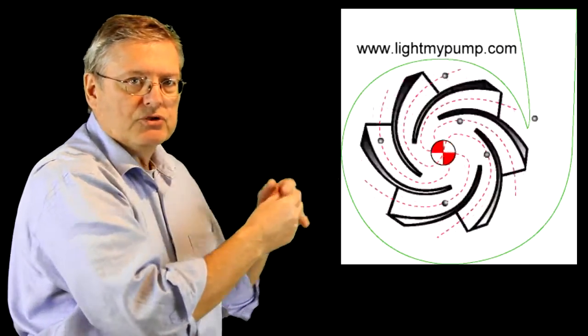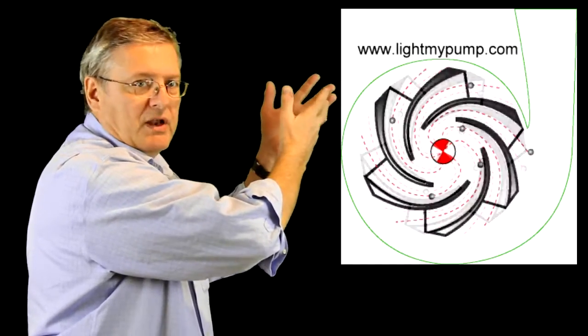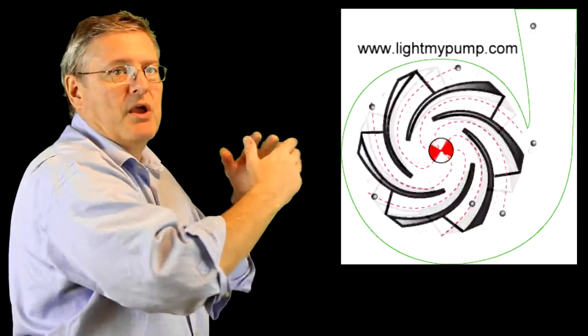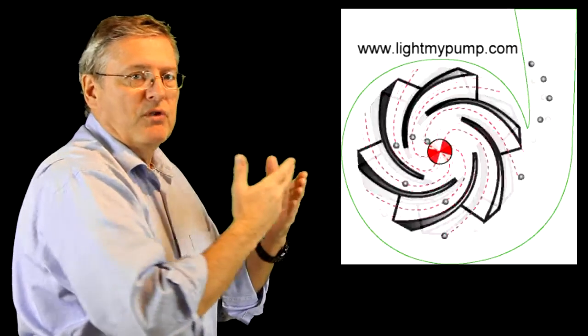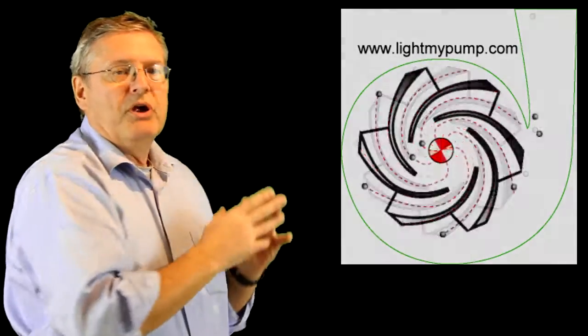The casing gets a little bit bigger, it's got this spiral shape called the volute and its function is to slow the liquid down to create pressure. As we know, if we create velocity energy and we reduce that energy, then it's going to go into pressure energy. So that's how we inject the energy into fluid: we create velocity energy and reduce that energy in the casing to get pressure energy, so we get a nice strong pressure at the discharge of the pump.